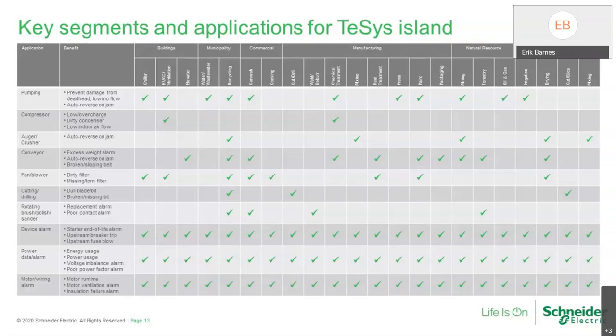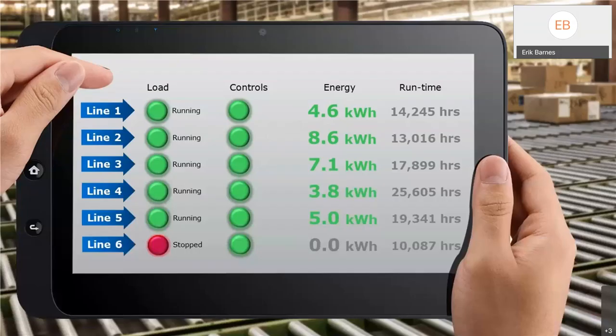So there's a lot of applications. This is actually just a brief snapshot, but we have all kinds of applications: pumping, compressors, augers, conveyors, fans and blowers, different things like that where we're using a motor to do some type of work, right? Depending on what that work is, what that load is, we can look for certain types of issues, right? And you think about the different segments and applications where these pumps, compressors and conveyors are used. It's all over the place, right? There's also the things we talked about as far as device alarms, monitoring the power, looking for motor specific issues. Those are all things that you can manage as well. So there's a lot of applications where you can use this to really enhance the machine.